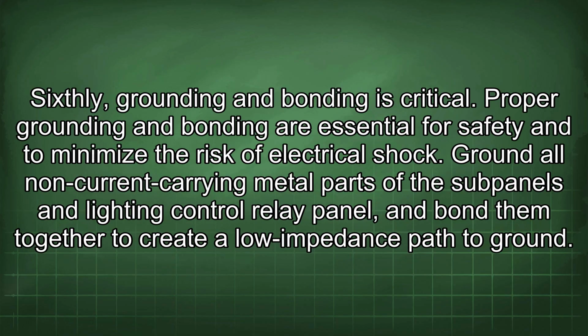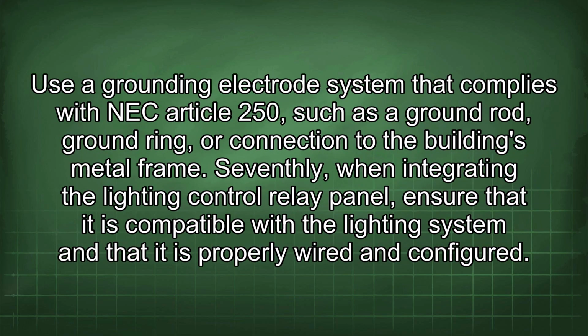Sixthly, grounding and bonding is critical. Proper grounding and bonding are essential for safety and to minimize the risk of electrical shock. Ground all non-current-carrying metal parts of the subpanels and lighting control relay panel, and bond them together to create a low impedance path to ground. Use a grounding electrode system that complies with NEC Article 250, such as a ground rod, ground ring, or connection to the building's metal frame.